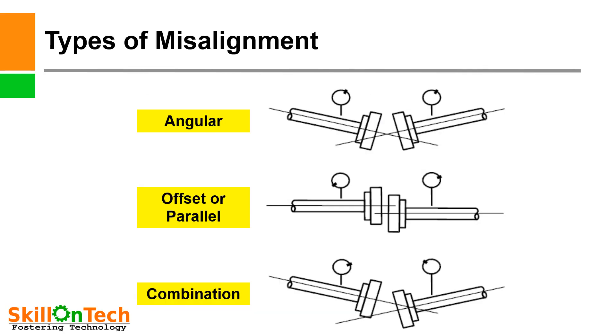Types of misalignment. Here in the first picture you can see angular misalignment — both the axes are at an angle; this is one axis and this is the other axis. This is the angle, so this is angular misalignment. This is offset or parallel misalignment — if your axes are up and down, that is an offset, because the axes are not in the same line.